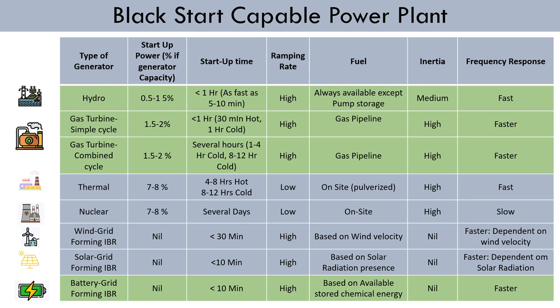Additionally, these plants possess the capability to swiftly adjust their power output by controlling the water flow. This agility allows them to adapt promptly to varying grid conditions and demands throughout the restoration process. The considerable size of hydro power plants, coupled with their substantial real power capacity, makes them capable of generating a significant amount of electricity. Consequently, they can effectively support the restoration process of the grid. Furthermore, hydro plants utilize the stored potential energy of water as their on-site fuel supply, eliminating dependence on external fuel sources during restoration. An inherent advantage of hydro power plants is their ability to provide excellent frequency stability and inertia.